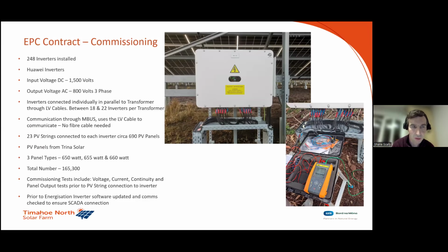So we have string inverters on site, 248 individual inverters. That's a little picture of them on the right hand side - you can see them mounted to the back of the table underneath the solar panels with the warning signs on, and the cables going in underneath, the MPPTs, coming from each of the strings, each solar panel string on the tables. The inverters are manufactured by Huawei. Input voltage on the DC side - the panels are connected in series, and there's 1500 volts going into the inverter on the DC side, and it outputs it then as a 3-phase 800 volts AC. So each inverter outputs that sort of amount, and they're all connected in parallel to the transformer centers through LV cables.